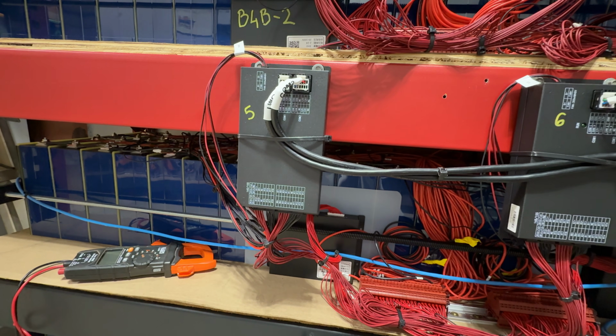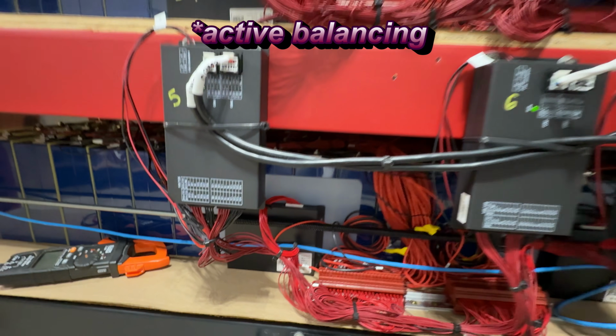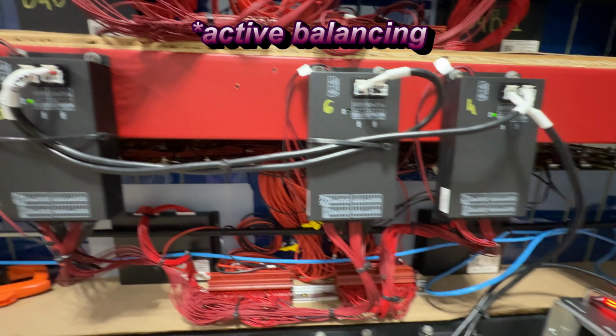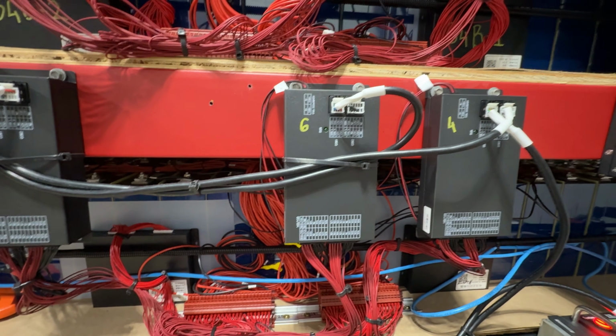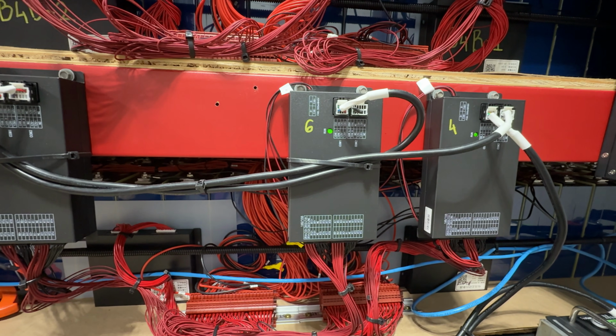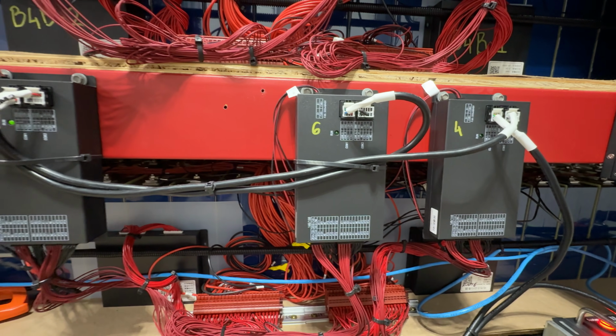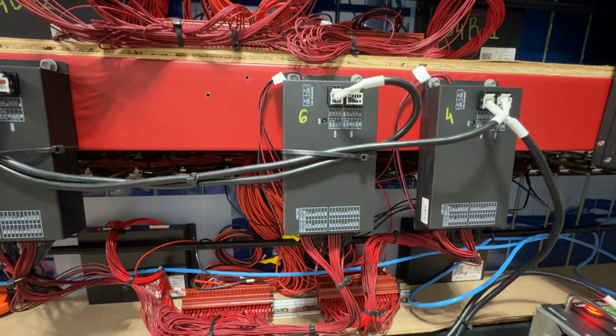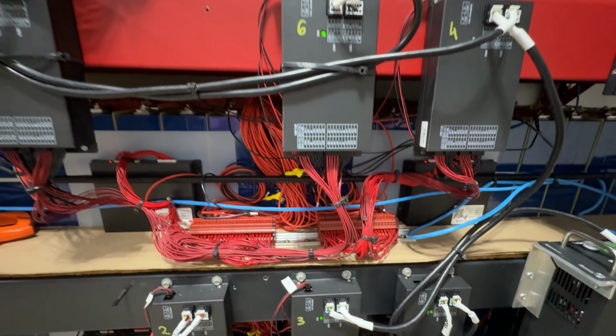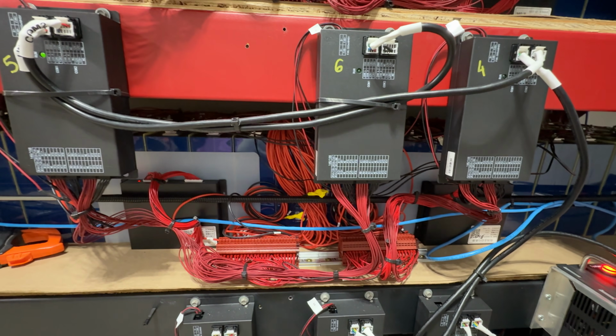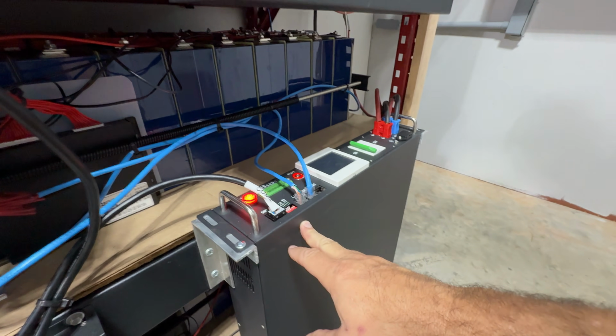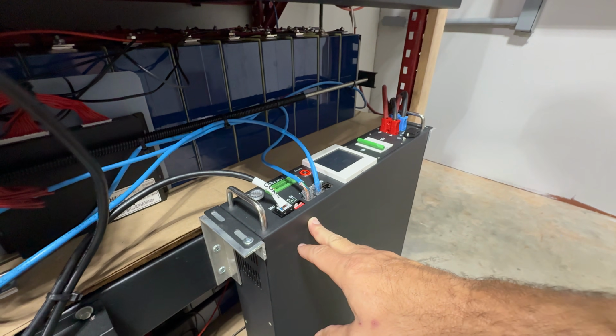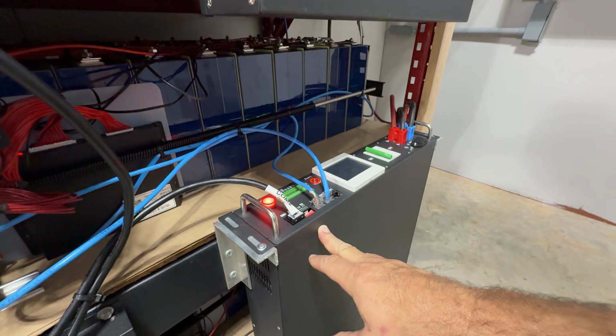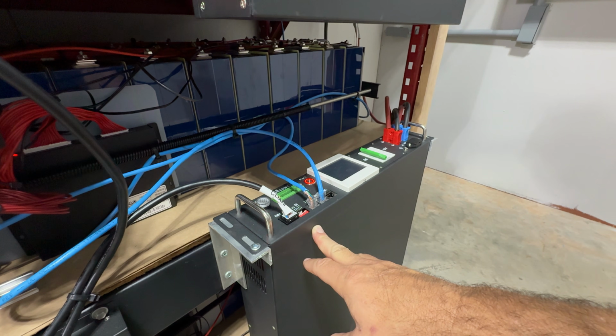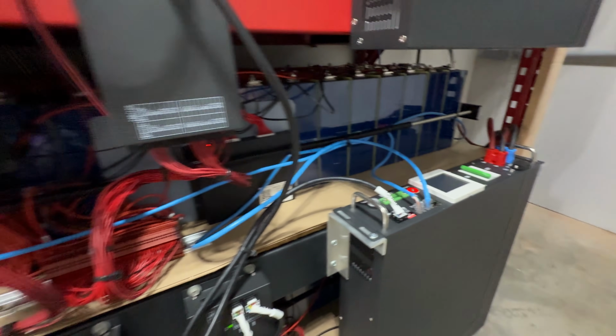They can do 200 milliamps worth of passive balancing, but these units do 4 amps worth of passive balancing. I would wish that these BMUs are capable of both, let's say active balancing of 3 to 5 amps, plus passive balancing, so they can get these 6 different modules of 16 cells to balance between themselves. This BMS is capable of that, capable of balancing the cells and then lowering the total voltage of one module. However, that works extremely slowly once you start talking about 280 amp hour cells.